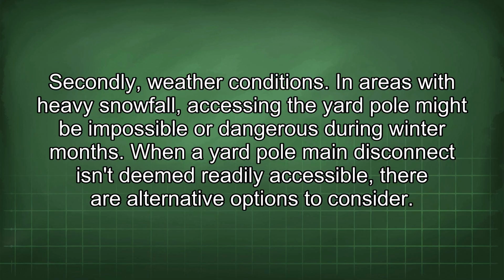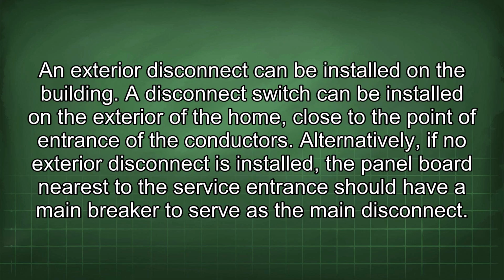When a yard pole main disconnect isn't deemed readily accessible, there are alternative options to consider. An exterior disconnect can be installed on the building. A disconnect switch can be installed on the exterior of the home, close to the point of entrance of the conductors. Alternatively, if no exterior disconnect is installed, the panel board nearest to the service entrance should have a main breaker to serve as the main disconnect.